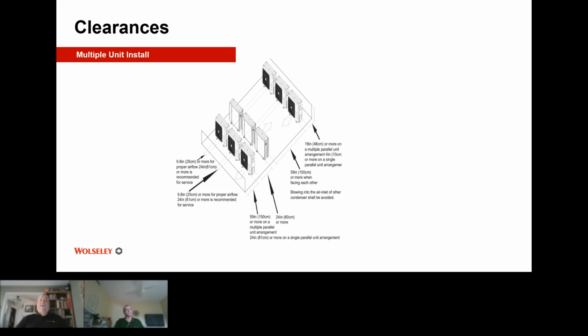As the LG person says before me in his presentations, we want to try and maintain proper clearances back to back and side to side. Now, it says here in some brand manufacturers that if you were to put them side by side, 10 inches would be adequate for minimum clearance, but we're actually looking for about 24 inches of clearance. So to a technician like myself, if there was ever a problem with one of these 9 units in the display, we want to make sure that they can A, take panels off, B, that they can get access to all the sides of the outdoor unit, and that they are not going to inadvertently affect another unit that they are crawling around and working on.